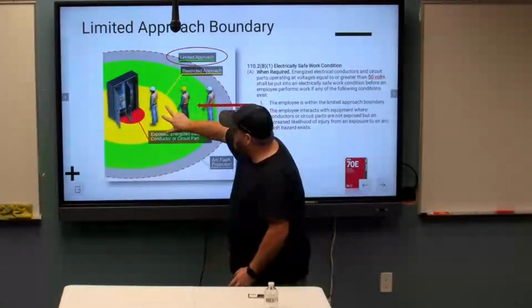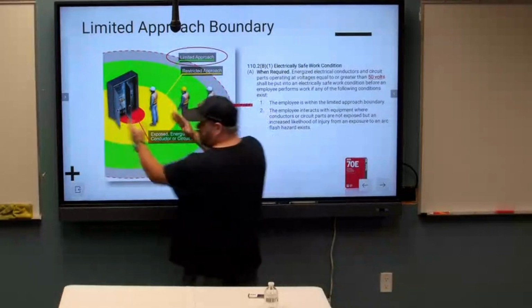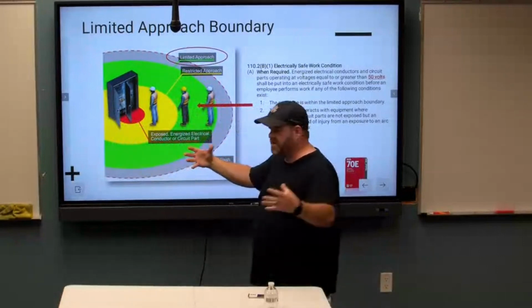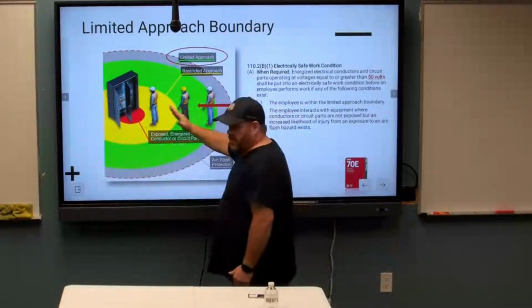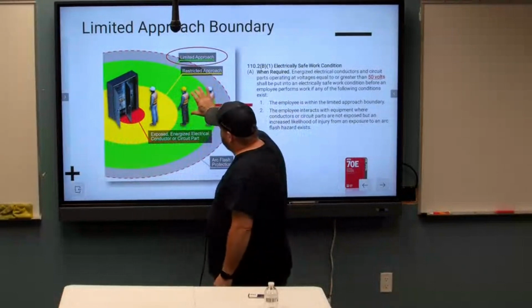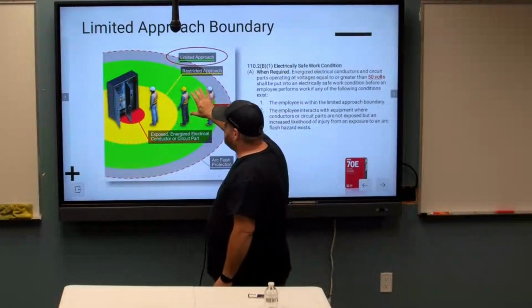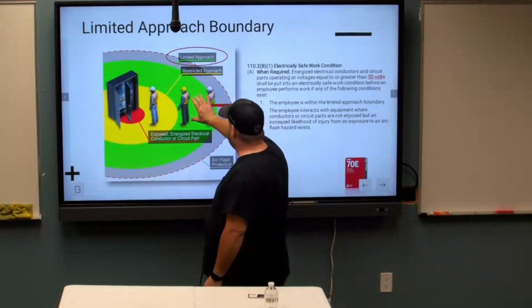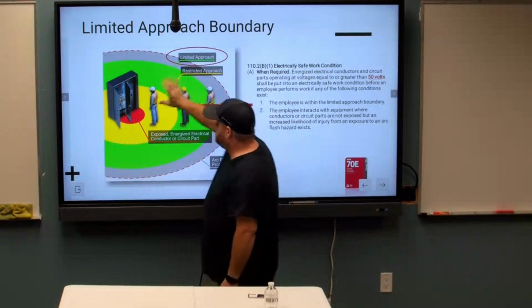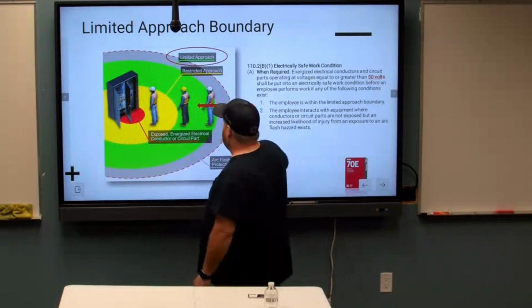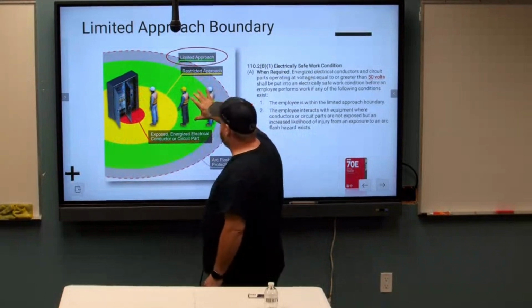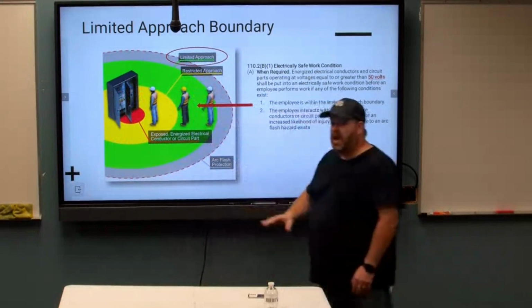And by the way, these boundaries aren't as big as what the picture shows. It's over exaggerated just to help you understand or learn the boundaries, okay? But your outermost shock protection boundary is called your limited approach boundary. So again, this standard says if we're going to be exposed to 50 volts or higher, and we're going to be in this limited approach boundary, we have to turn it off and lock it out.